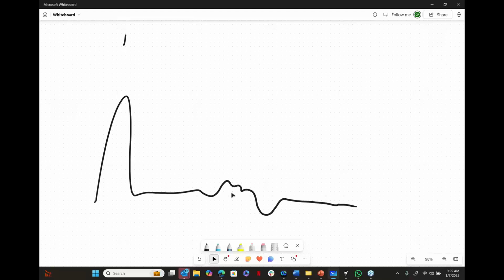So if you ever see a signature that looks like something like this, where it looks like something could be interrupting your signature, I want you to assume something could be interrupting your signature. If I were able to use some sort of zoom window here and zoom in on that and expand that picture, I might find that upon closer evaluation, there are actually two events in one here. If I were to spread that out, I could see that there were two separate signatures.